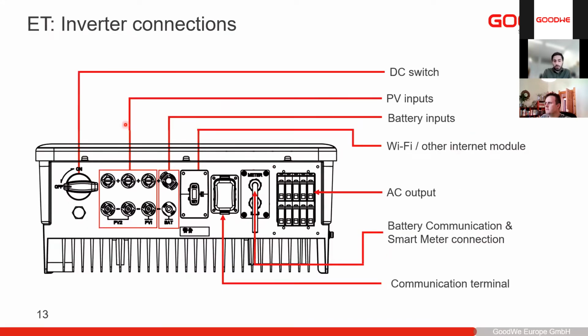All connections to the inverter are on the bottom side. In some specific cases, you also have some DC switches on the side of the inverter. However, for all storage inverters, it's always on the bottom side. So here you see the DC breaker, and then here you have the different PV connections. This is an ET inverter, and here you see that you have 3 different PV connectors actually. So there are 2 different MPPTs.